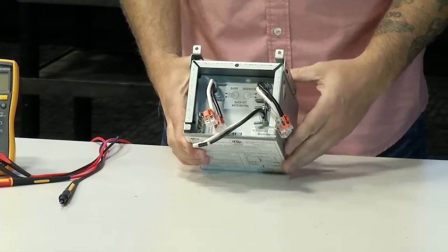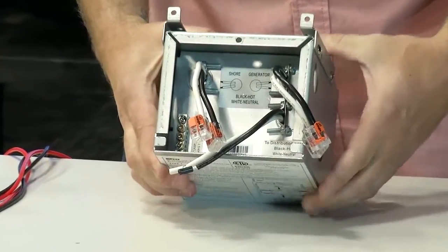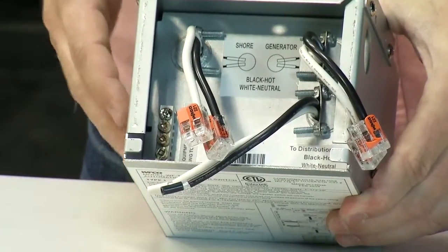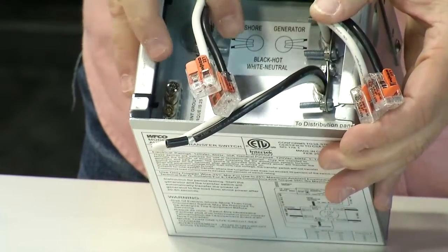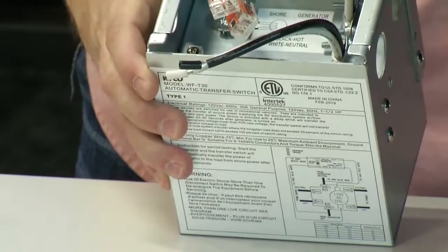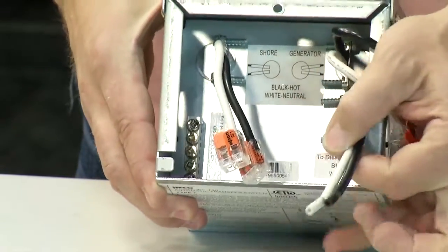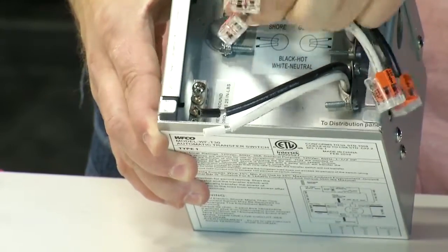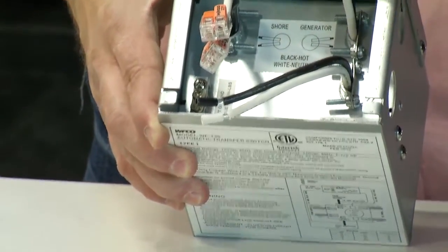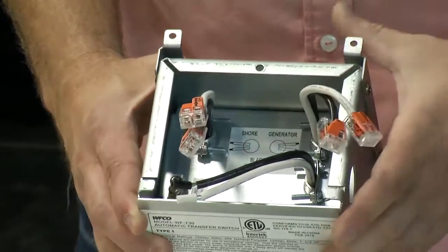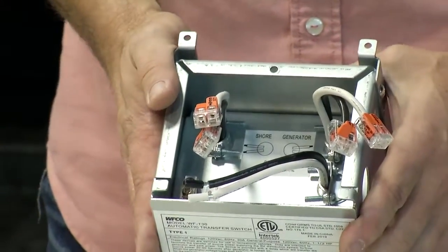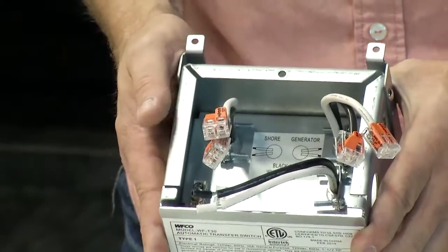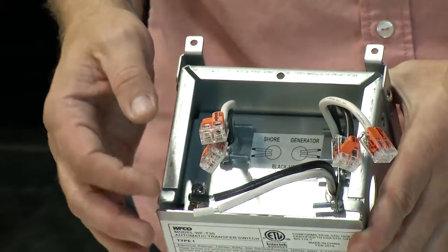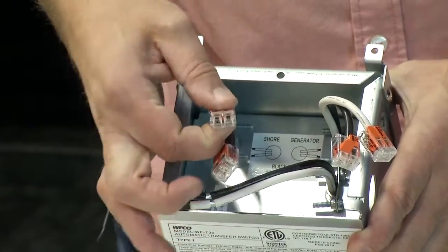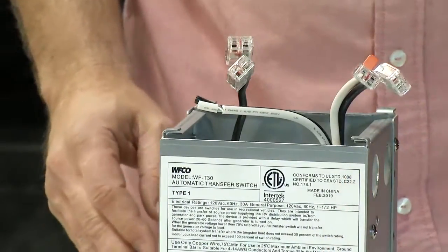And if we can zoom in on here, there we go. It's going to be labeled. So you have a label right here that's indicating your shore power. This one's going to be indicating to your distribution panel. And these are your generator wires over here. In a transfer switch, your generator leg is going to be primary. So when you start up the generator, the relay inside is going to switch over and pass through your generator wires.